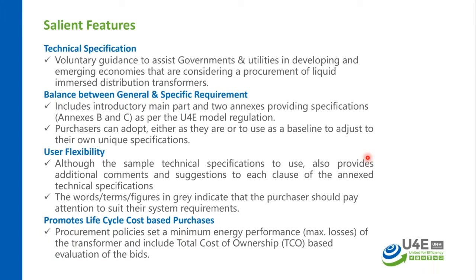The sample technical specification provides the necessary comments illustrating the need for each clause, and it is annexed with the specific technical requirement against that particular clause. It also provides the flexibility of including your own values, such as voltage level, the highest system voltage level, the basic insulation level, etc., in the spaces provided in gray, so that you can just enter the values there and use this document for your purchases.